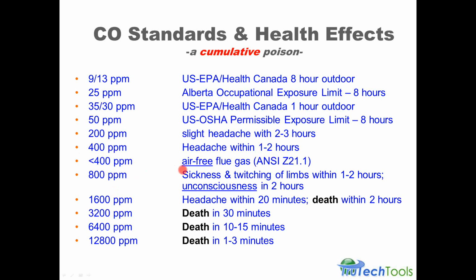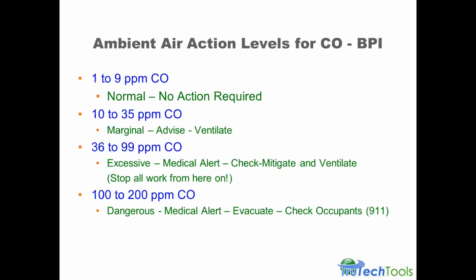We also threw in here the ANSI standard, the ANSI Z21.1 standard, which is for the air-free flue gas measurement for combustion appliances, and is required to be less than 400 parts per million when measured on an air-free basis. We'll get into that in some of the upcoming slides when we talk about appliance testing. But this is just to give you an overview of the levels that governments want to see you exposed to versus the health effects.